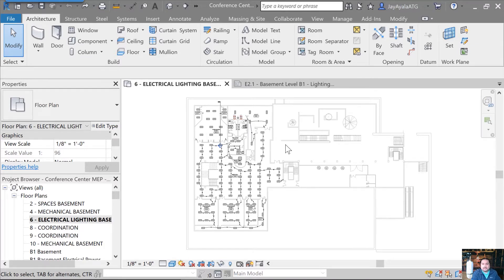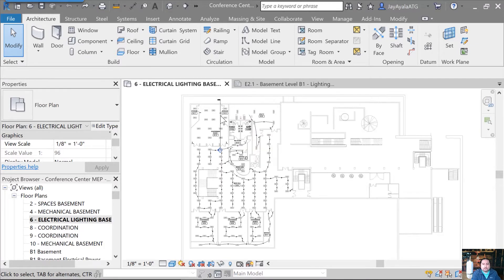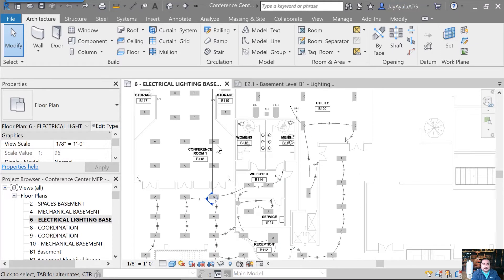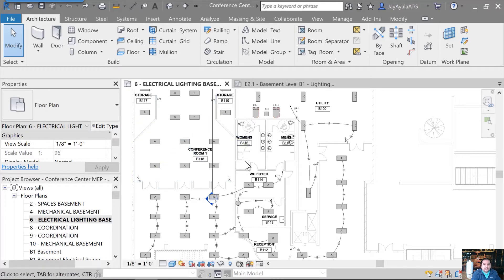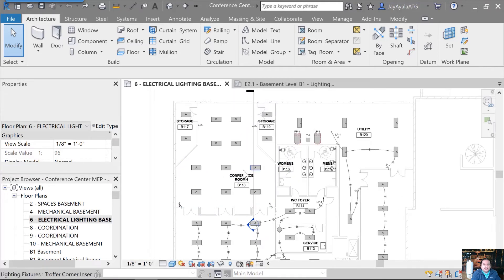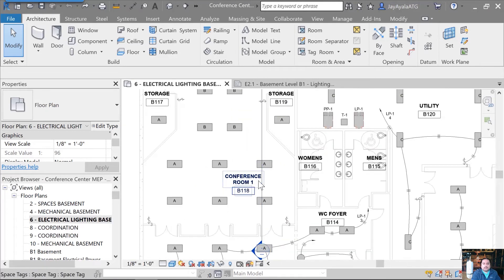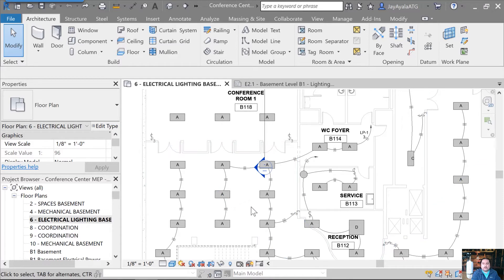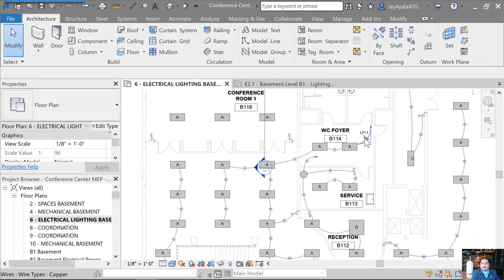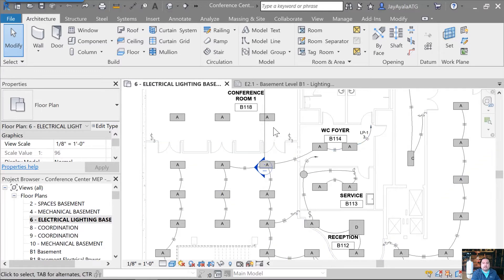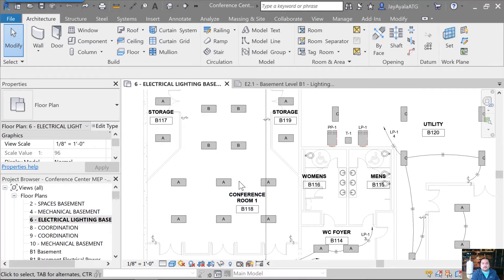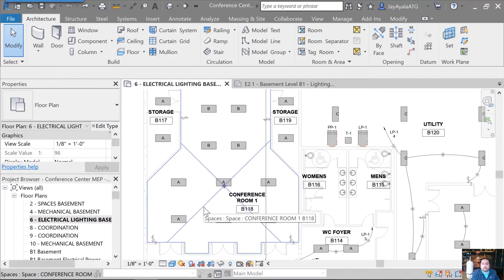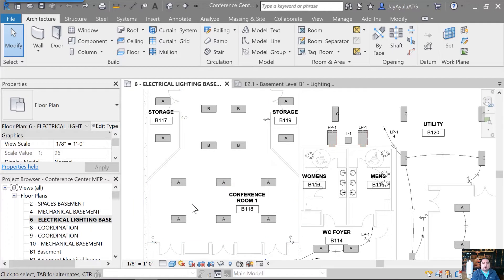Here I've got a floor plan in Revit and we are looking at a conference room. In this conference room, as you can see this other area, everything is wired up and it's already circuited. You can see that we've got the lighting here on panel LP1-3. This other conference room, conference room 1, room number B118, it doesn't have anything circuited yet. So how do we do that?